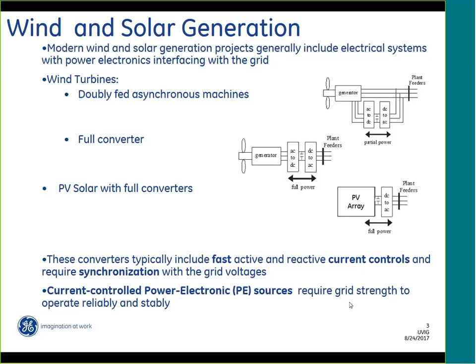What does that mean? Grid strength can be understood in several ways. Here we're talking about the strength of the voltage. If at a particular bus of the system I inject a current and the voltage at that bus is not significantly affected, that system is strong—it's a strong network. On the contrary, if the voltage at a bus is significantly affected by the current I'm injecting, then that bus is weak with respect to the level of current being injected. So in today's presentation, when we refer to grid strength, we mean the strength of the voltage against the injection of current.